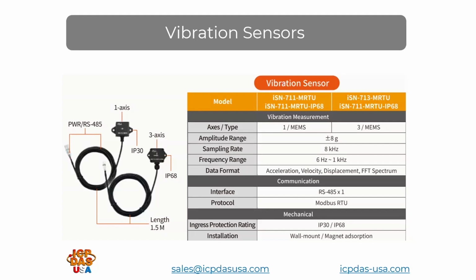MEMS are used for contact applications. They are mounted on the machines that they're used to detect vibrations on. MEMS stands for Micro Electromechanical Systems, which are tiny devices that integrate electronic circuits, sensors, and moving parts onto a single chip. They're fabricated using semiconductor fabrication techniques. ICP DAS uses the MEMS technology in their vibration sensors. We also have the IP68 version, which is water and dust resistant.